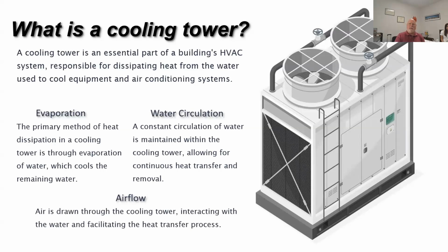So whatever the equipment is that needs heat rejected, for example, a heat pump, will have water circulating through it, and that water will then take the heat to the cooling tower, where the hot water will come into the tower, and depending upon the tower, will drop through and through the evaporative process will cool the water and send it back out into the system. And so again, evaporation is the key process here.